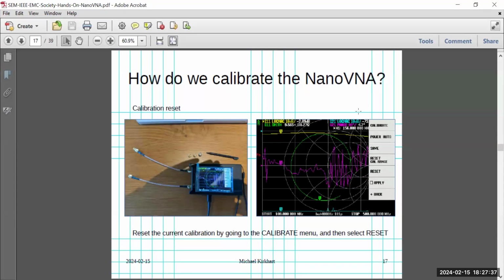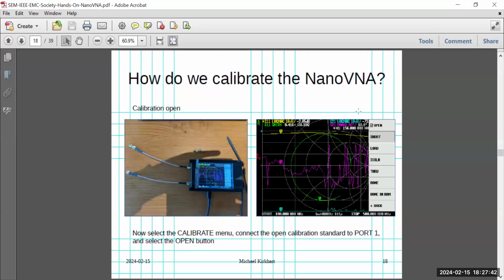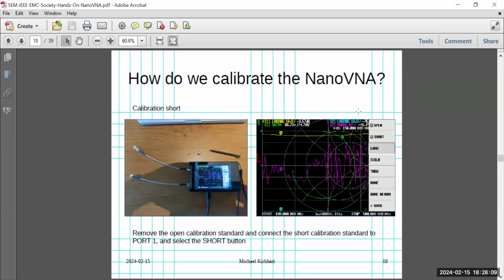When you're in this menu and you hit calibrate, it'll bring you to this menu over here. Is everybody able to get to that? Okay, so once you have the open standard connected, then press open. What you'll see is some progress bar come across, and when it's finished, you'll see a check mark and it'll automatically go to the short. So the next one, as you can probably guess, is the short. Now, I'm assuming you guys can figure out which one is the short. It does have a pin on it. Yeah, exactly. So once you get that connected, go ahead and just press the short button. And if all goes well, you'll see it get checked off.